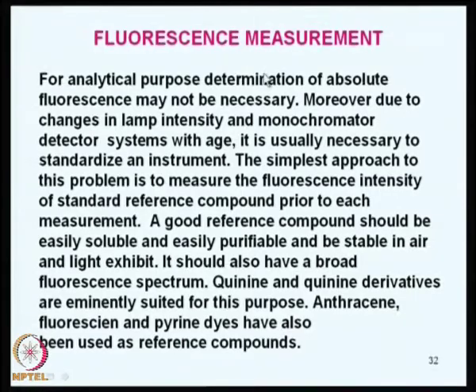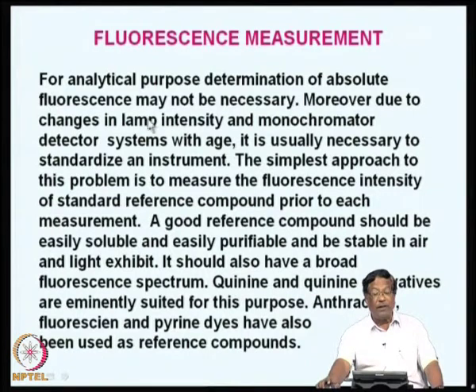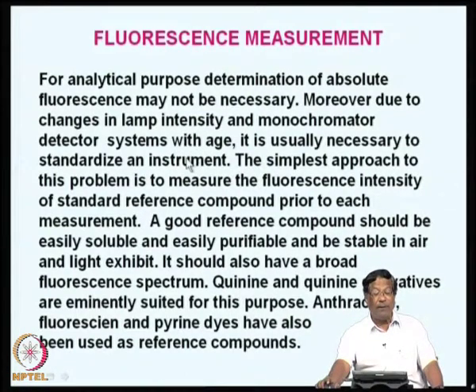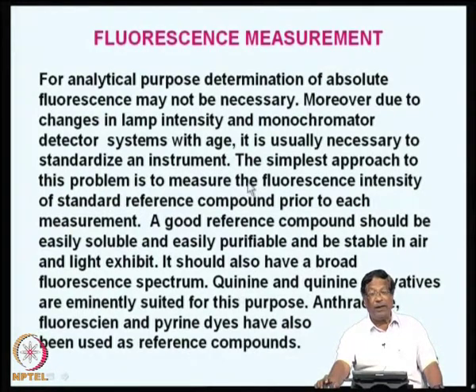Welcome to the next session of our discussion on fluorescence methods. We will continue our discussion on fluorescence measurements. For analytical purposes, determination of absolute fluorescence may not be necessary. Moreover, due to changes in lamp intensity and monochromator detector systems with age, it is usually necessary to standardize an instrument. The simplest approach is to measure the fluorescence intensity of a standard reference compound prior to each measurement.